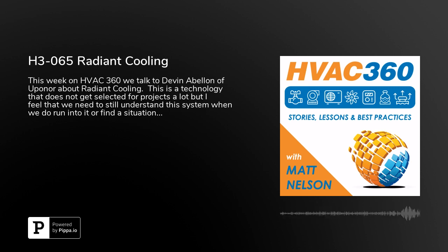Sure. I was joking, but it comes up quite a bit. It's probably one of the first things that comes up when people bring up radiant cooling: what about condensation? How are we going to deal with condensation? Obviously, we don't want condensation. We get wet floors and people slipping. You can run into mold issues with carpet and wood damage on wood floors. So we need to make sure the system is designed such that we don't get condensation. But you really have to take a few steps back and ask yourself, when would condensation occur?